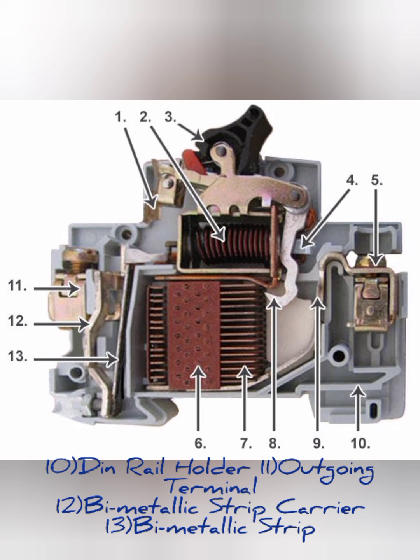The 12th one is your bimetallic strip carrier, and the 13th one is your bimetallic strip. The bimetallic strip is used because it expands and shrinks according to its thermal level, which means whenever overheating is produced, the MCB automatically gets tripped. The bimetallic strips respond to the temperature level of your MCB, which means the incoming and outgoing loads. So these are all the basic parts of your MCB.